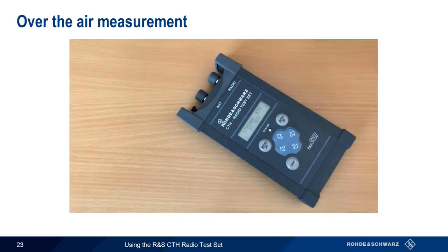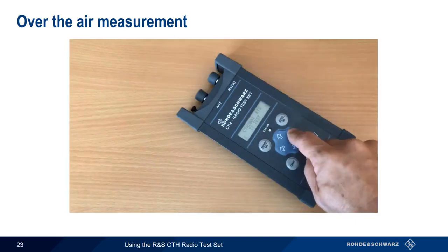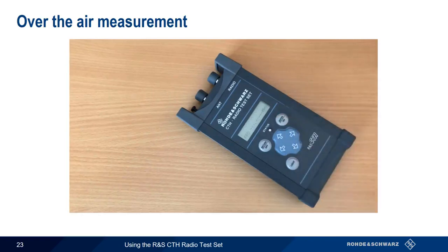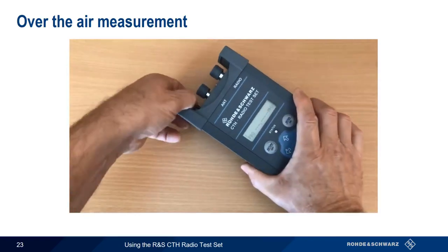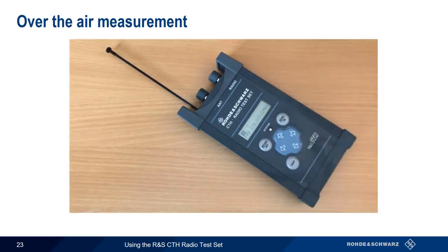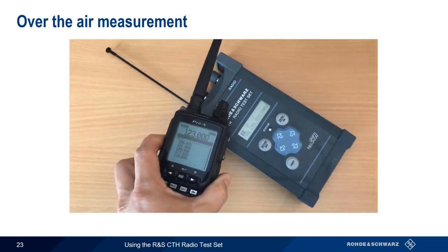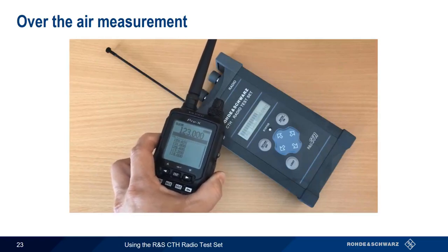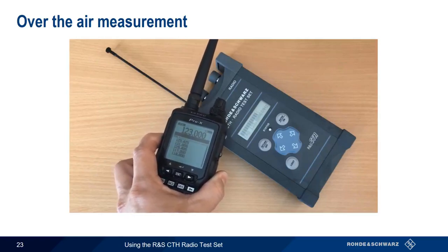We start an over-the-air measurement by first entering the over-the-air test mode. The next step is to fully extend the CTH's built-in antenna. The frequency and field strength measurements begin automatically. If we key up a nearby transmitter, the CTH measures and displays the frequency and field strength. No cable connection is required.